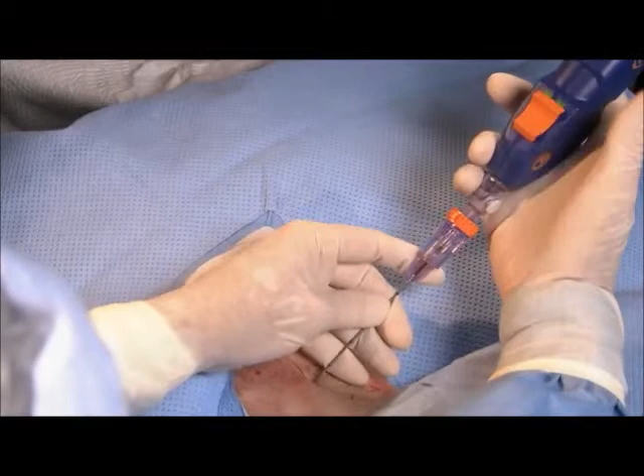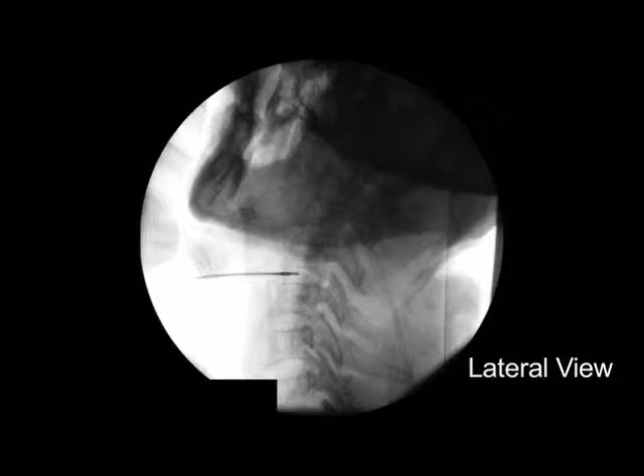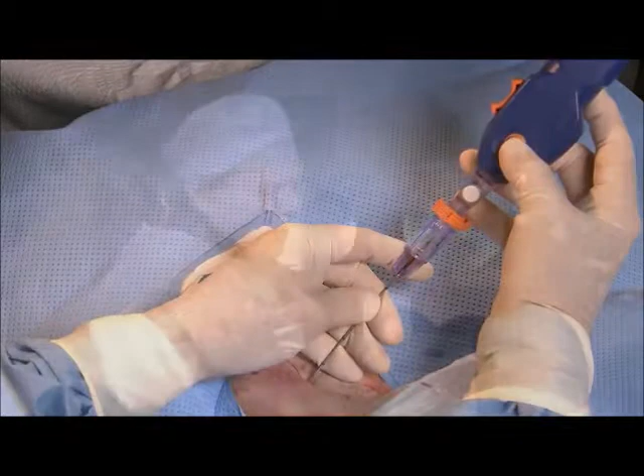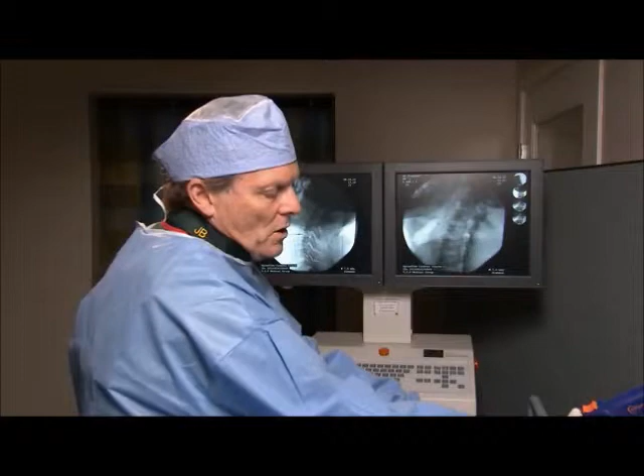As I deploy the cutting tip 1.5 millimeters with this orange slider, you'll see the tip on the x-ray advance more into the middle in this lateral view. This is the position that the cutting tip should be in when you start the motor and start to advance and retract the system within the limitations of this limiting device, which is 5 millimeters. So if you see the x-ray, you will see that when I push forward, I'm still well within the nucleus. When I retract, I'm still within the nucleus.